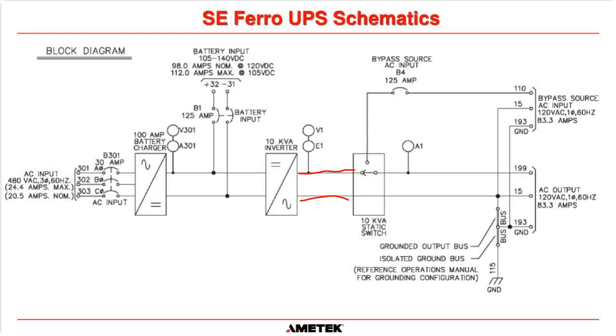Now, whenever I go through any presentation on UPSs, people always get confused with the static switch and what we call the RMBS, which is the remote manual bypass switch. And the way that I try and get you to remember it is static switch. Remember static. Static means there are no moving parts. Okay, it's not static electricity. It's static as in there are no moving parts. Okay, so the static switch is an electronic switch that chooses between inverter operation and bypass operation automatically.